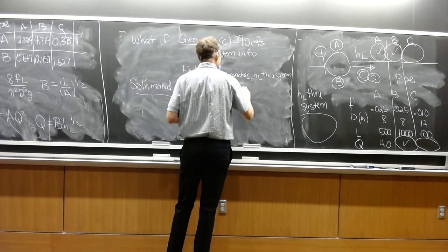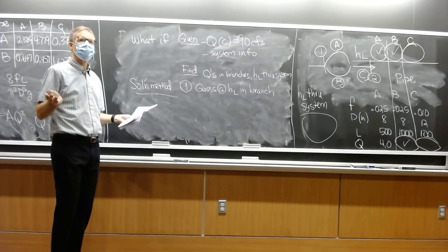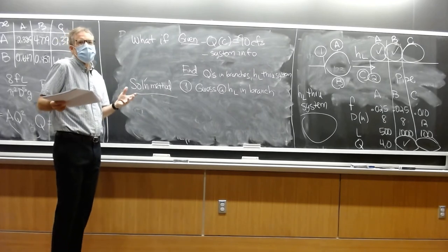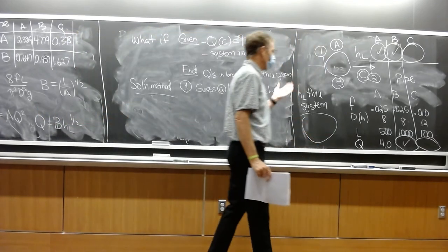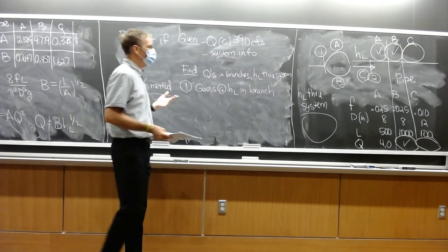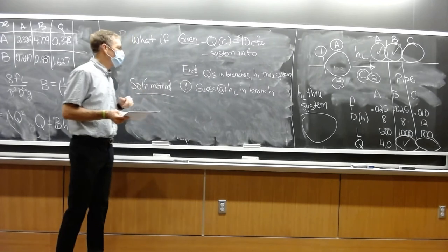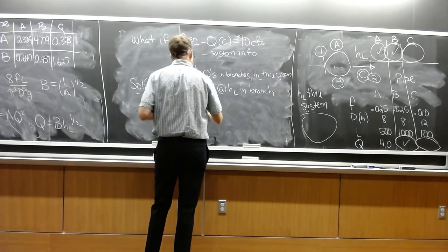What we can do is guess at what the head loss is through a branch, okay? And you can make a reasonable guess based upon the flows that you have. We had a situation where the total flow was only 6.83. So we might guess that the total head loss through the branches is something larger than what we previously calculated, 38 feet. So I'm just going to guess that the head loss in A and the head loss in B is 50.